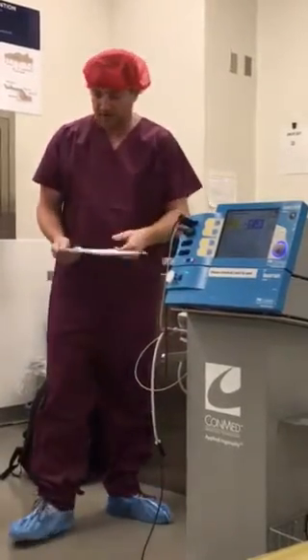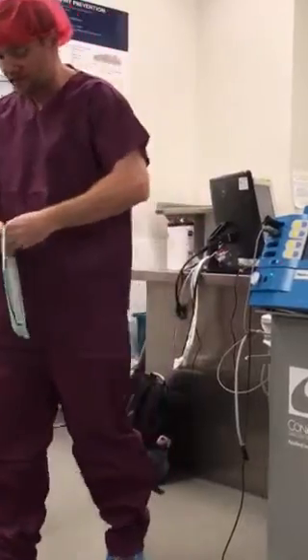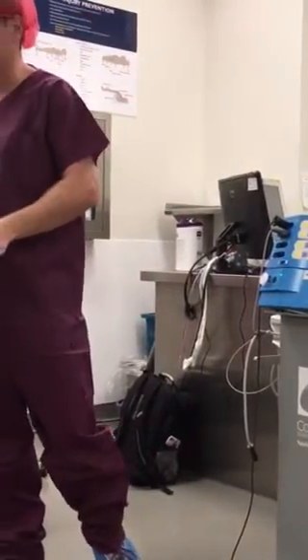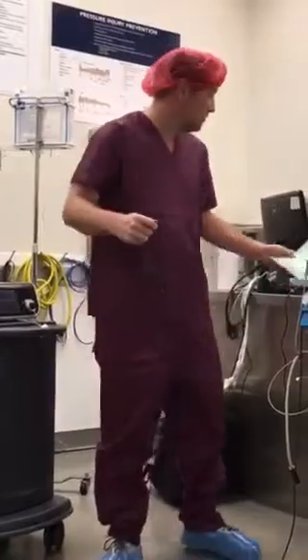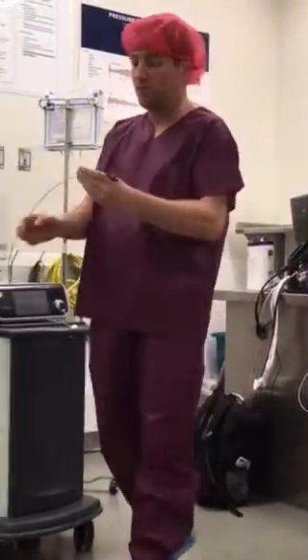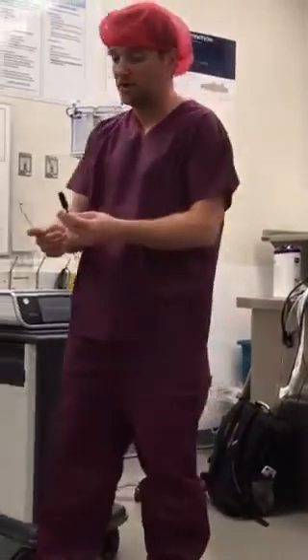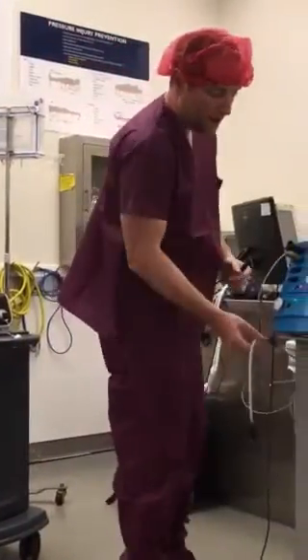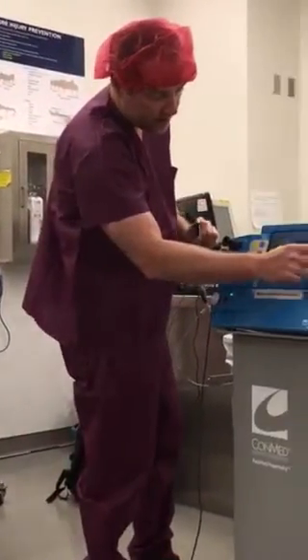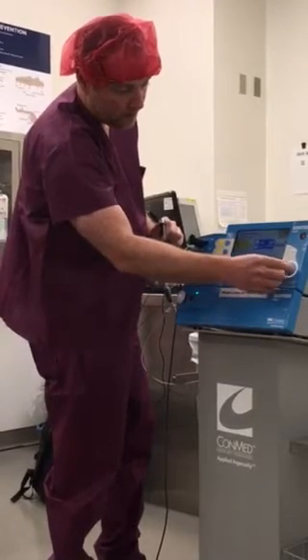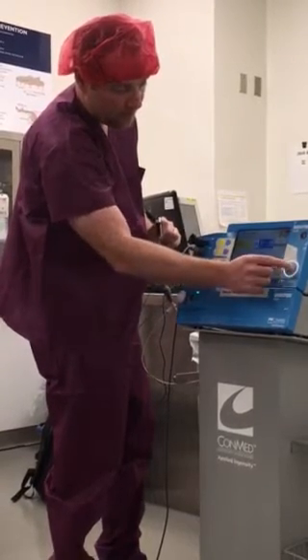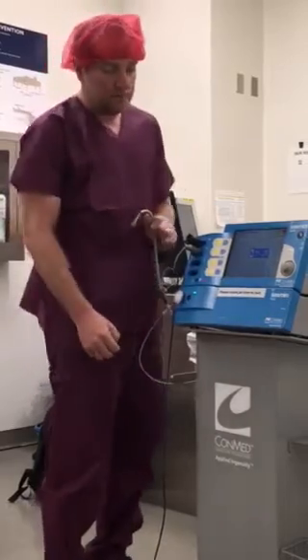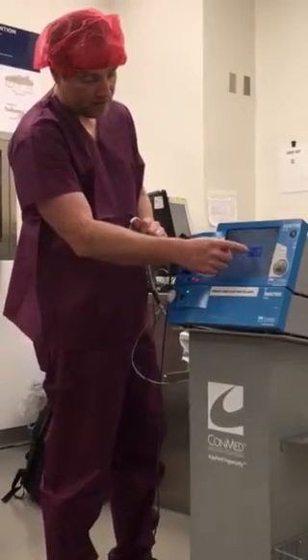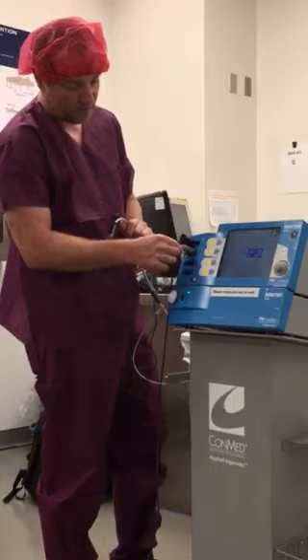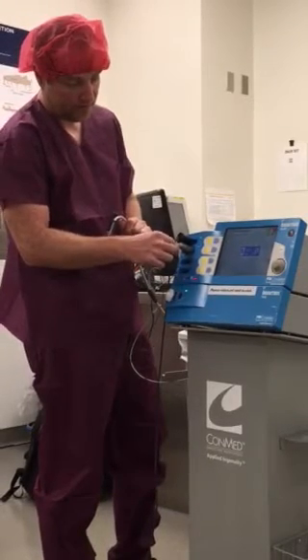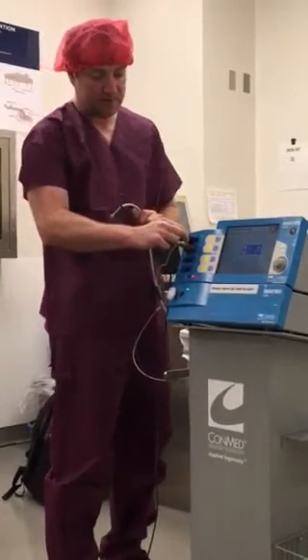We also have a probe that is designed for a typical pulmonary procedure. This could be used in a regular bronchoscope because it's got the 1.8 millimeter diameter, so it'll go down the smaller channel. And this, you're going to have to actually change the setting on here to pulmonary argon. You do that by hitting the menu button, move this down, highlight pulmonary argon. And as you see now, this is going to go on the second row. The second row means it is going to be worked by this cord right here. The last one is on the top row, so it's being worked by this monopolar active cord.